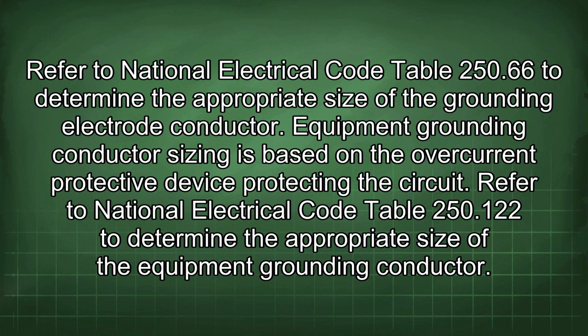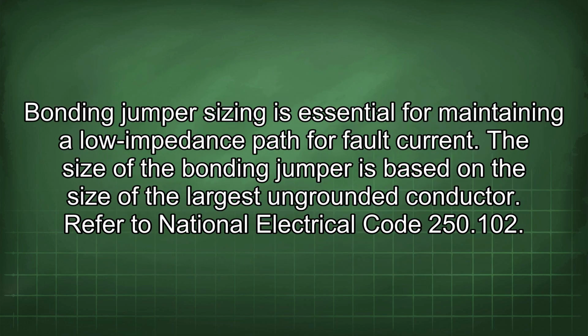Equipment grounding conductor sizing is based on the overcurrent protective device protecting the circuit. Refer to National Electrical Code Table 250.122 to determine the appropriate size of the equipment grounding conductor. Bonding jumper sizing is essential for maintaining a low impedance path for fault current. The size of the bonding jumper is based on the size of the largest ungrounded conductor.